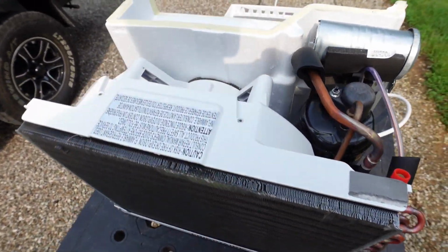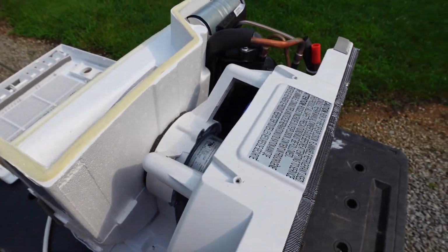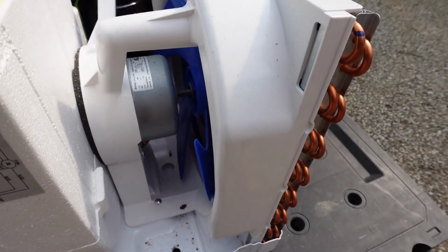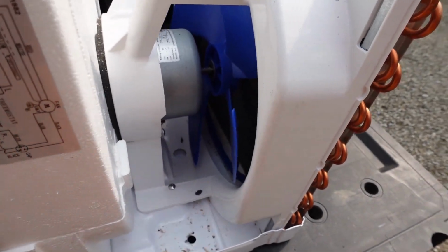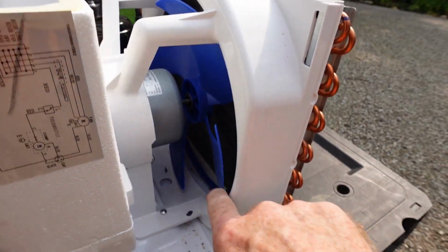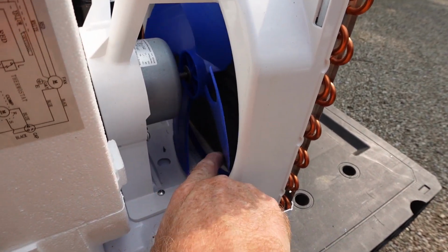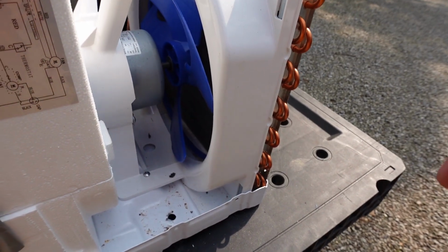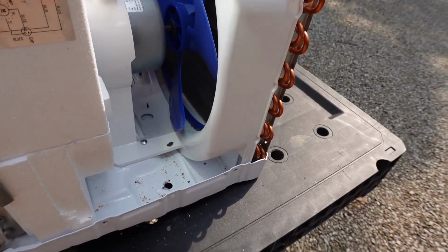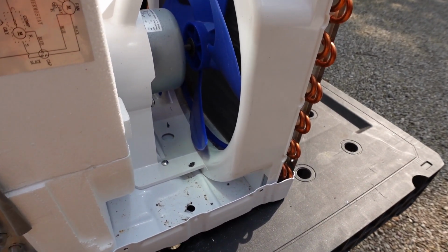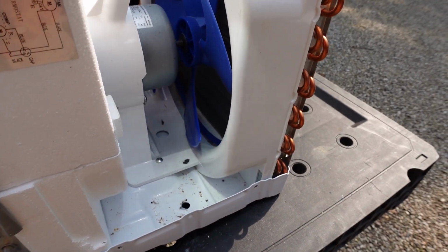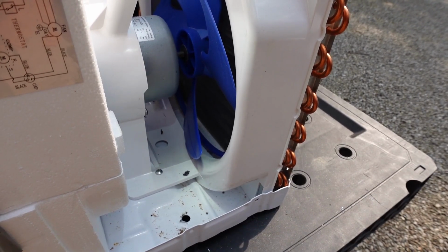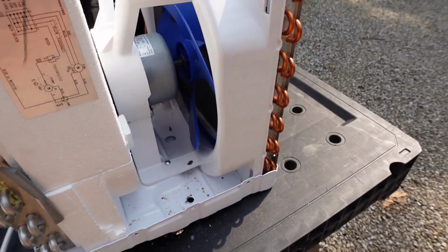Thank you, sir. So when I got it off and I started looking at it, at this point it's easy to see the slinger ring inside the fan. And let me see if I can show you guys. It's this blue ring right here that attaches to the fan blades down the inside. Trying to film in the sun is just kind of a bear. But you can see that slinger ring in there, and that is designed to pick up that water and direct it outside. Now here's where it gets really interesting.